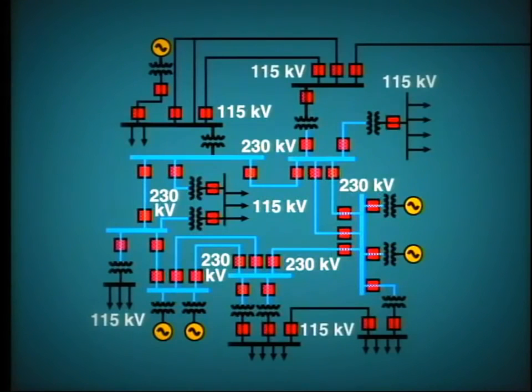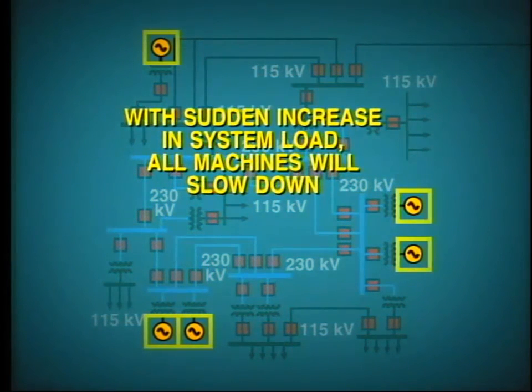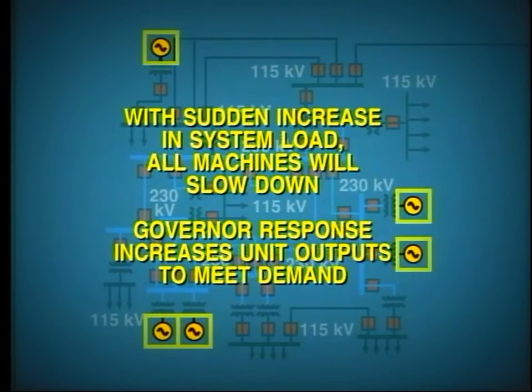Most of the machines on the system — that is, steam turbines, gas turbines, and hydro turbines — will operate on governor control. If there is a sudden increase in system load, all of the machines immediately slow down, and this is immediately detected by the governors. Governor response opens up the fuel inlet or steam inlet valves, and so increases the unit outputs in order to meet the increased load demand. This action takes about 10 seconds to stabilize.